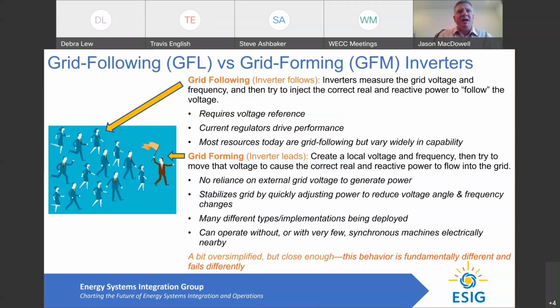And as grids get weaker, it is more complicated and more difficult for the current regulators to maintain their stability. There are certainly a lot of tricks and tweaks that can be made for this, but that's where the grid forming inverter can come in to help manage a lot of the stability concerns about the control in weaker systems. Grid forming is different from grid following in that there's no reliance on external grid voltage to generate power. It can actually generate its own voltage reference and quickly stabilize the grid by adjusting a voltage reference and frequency in order to deliver its power.